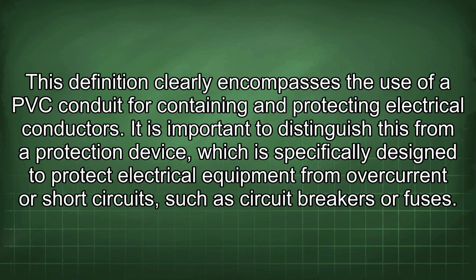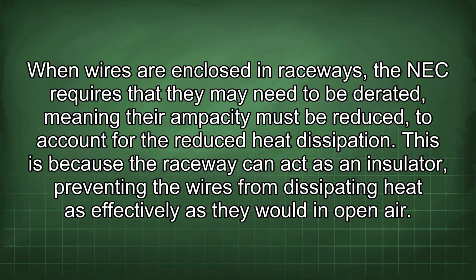It is important to distinguish this from a protection device, which is specifically designed to protect electrical equipment from overcurrent or short circuits, such as circuit breakers or fuses. When wires are enclosed in raceways, the NEC requires that they may need to be derated, meaning their ampacity must be reduced to account for the reduced heat dissipation.